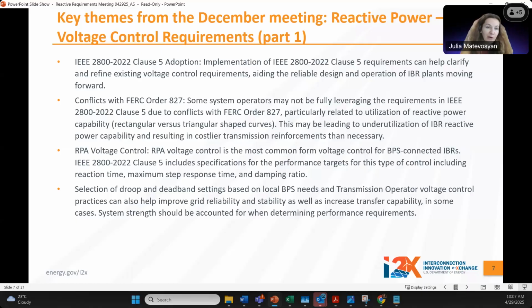This is particularly related to utilization of reactive power capability. 2800 requires rectangular reactive capability, while FERC Order 827 requires triangular shape curves. This may be leading to underutilization of IBR reactive power capability requirements and result in costlier transmission reinforcements than may be necessary.